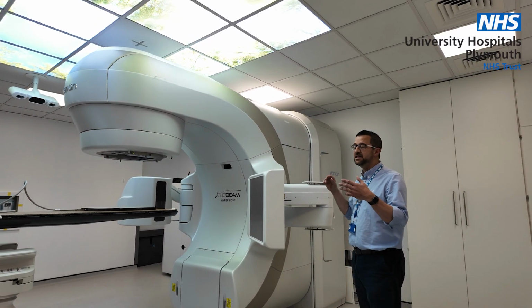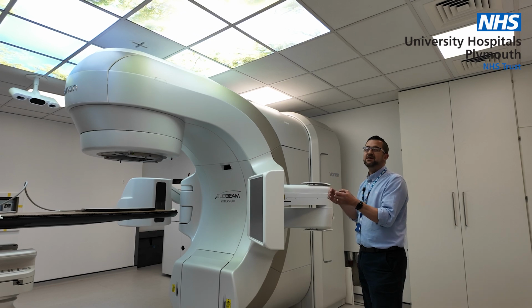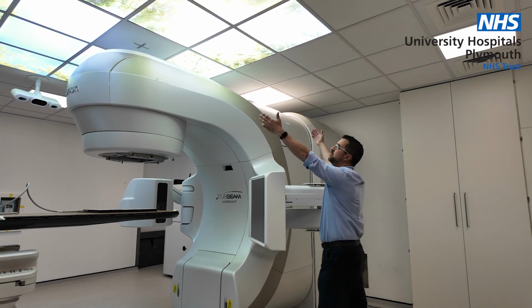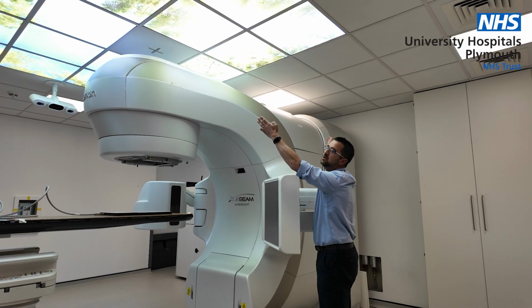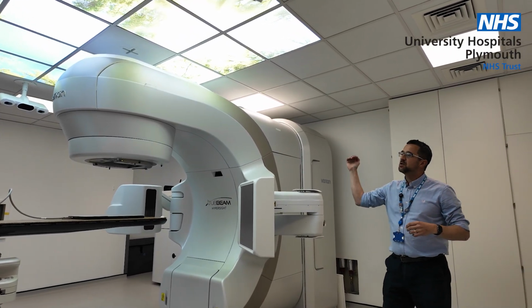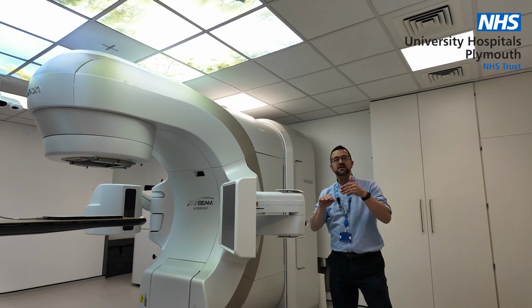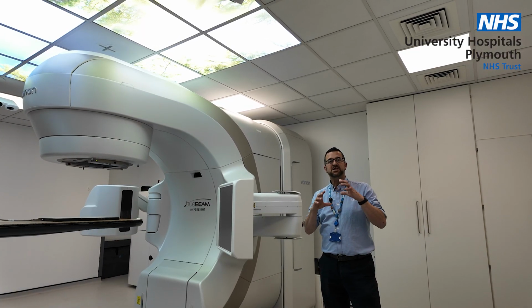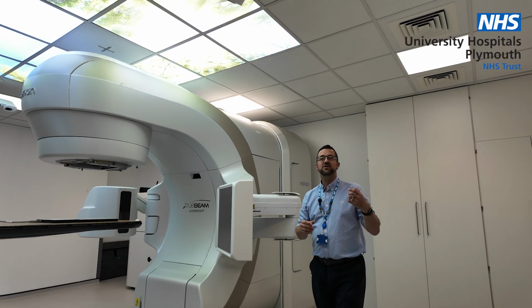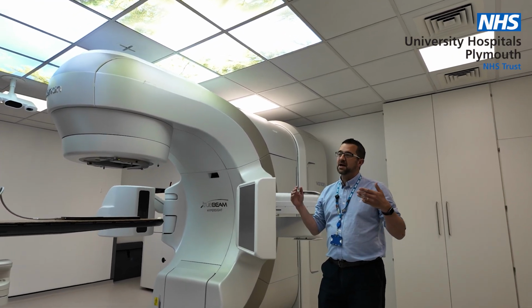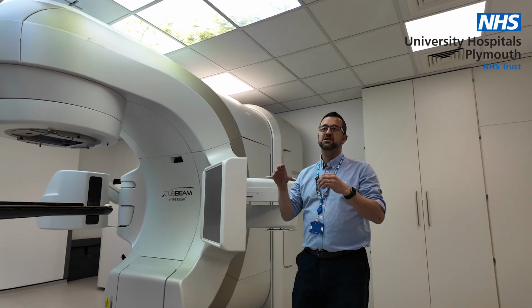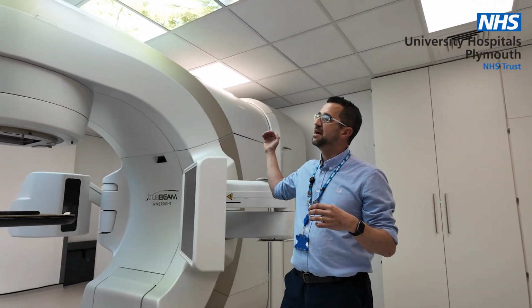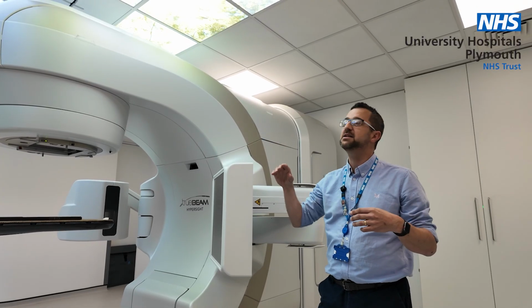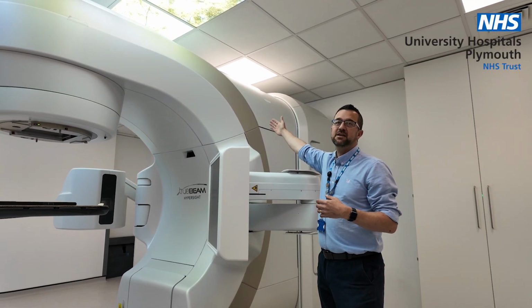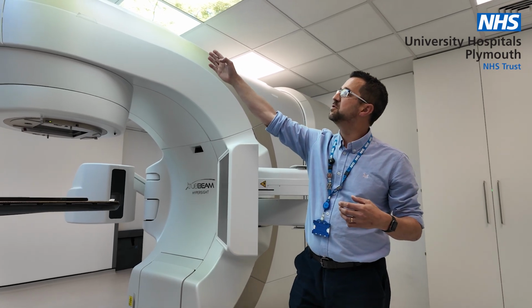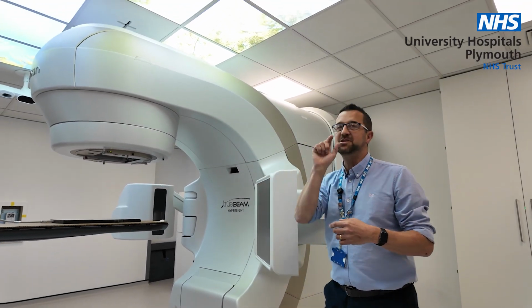So actually the accelerator, this is a linear accelerator, shortened to LINAC, the name. The actual accelerator guide is only in this top part here. It's about 4 foot long, and we inject the microwave RF power into the back end of it, and we coincide that with electrons which are generated from the electron gun by thermionic emission. And that coincidence of those two, the electrons and that RF power, accelerates the electrons through the accelerator guide. And we inject them in at about 0.4 the speed of light at this end, and we accelerate them all the way up to almost the speed of light.